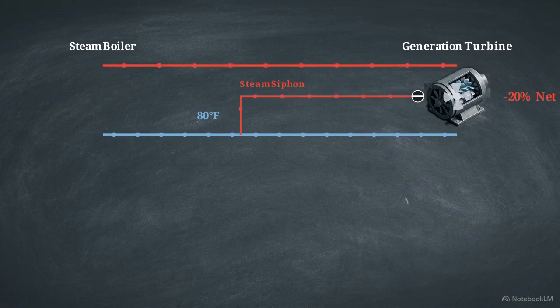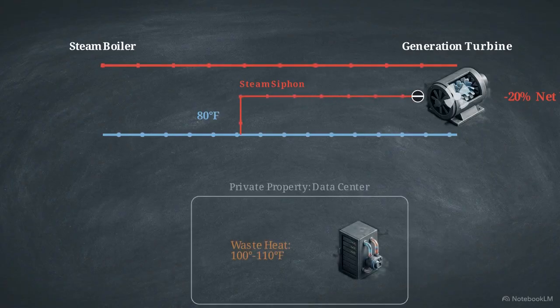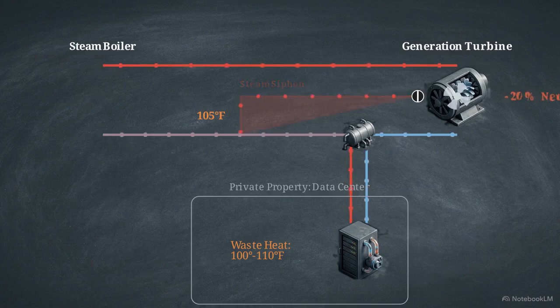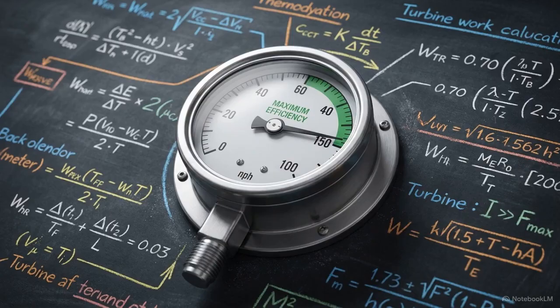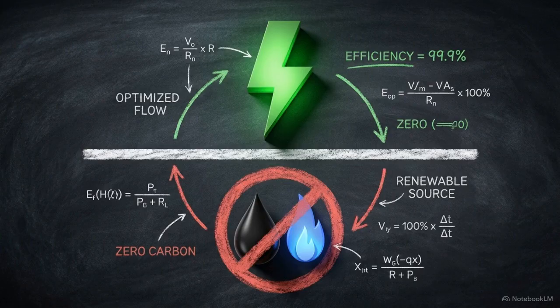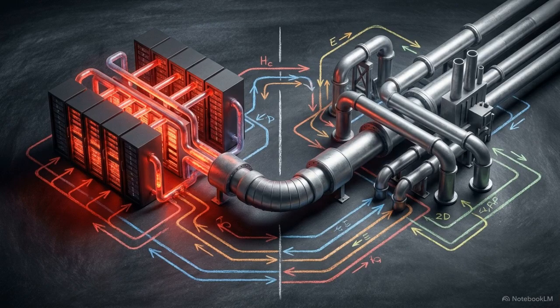A co-located data center utilizing a direct-to-chip liquid cooling loop captures server waste heat at a stable 100 to 110 degrees Fahrenheit. This heated liquid is piped into a liquid-to-liquid heat exchanger at the power plant's cold water intake. The data center's thermal waste transfers into the incoming feed water, pre-warming it. The power plant automatically detects this temperature increase and drastically reduces internal steam extraction. The saved high-pressure steam remains inside the turbine housing, driving the generator blades longer and resulting in a surge of turbine work. This optimized loop enables the power plant to output more net megawatts of electricity into the grid using zero extra fuel consumption. By capturing and reusing low-grade thermal exhaust, behind-the-meter co-location transforms a standalone data center into a highly efficient thermal partner.